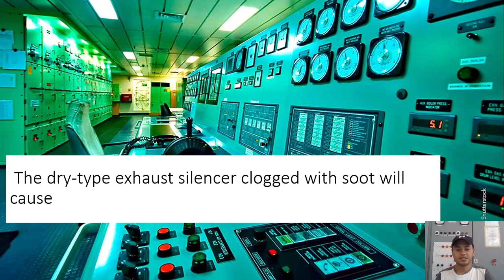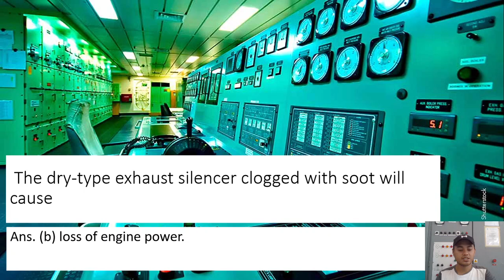Okay. Next, the dry type exhaust silencer clogged with soot will cause loss of engine power. So when the dry type exhaust gas silencer gets clogged with soot, the flow of the large amount of exhaust gas is restricted, and because of that, the exhaust gas pressure will be higher. The complete removal of exhaust gas will not be possible, which will cause the mixing of the exhaust gas with the incoming air. Thus, it dilutes the incoming air with the exhaust gas. This will cause improper combustion because of the starvation of oxygen for the combustion of fuel. The exhaust temperatures will increase and consequently there will be loss of power in the engine.